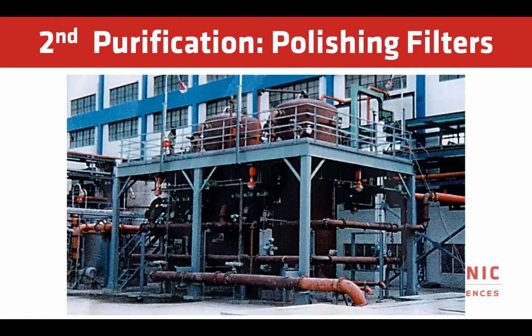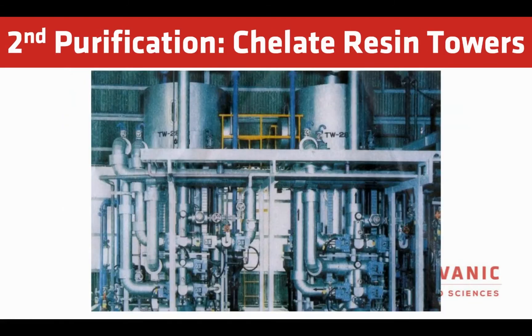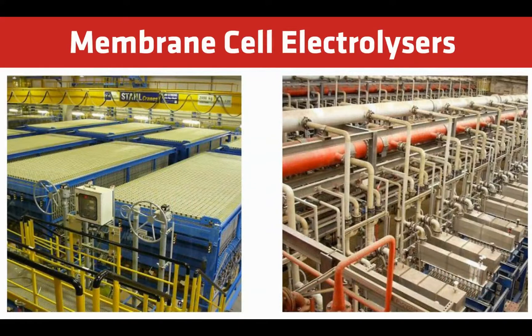Next, the brine receives secondary purification. The first step is polishing filtration, which reduces suspended solids and protects the ion exchange resin from damage. The chelating ion exchange resin treatment then reduces hardness down to low ppb levels, allowing the brine to enter the membrane cell without causing any damage. Finally, the purified brine can enter the membrane cell for electrolysis.